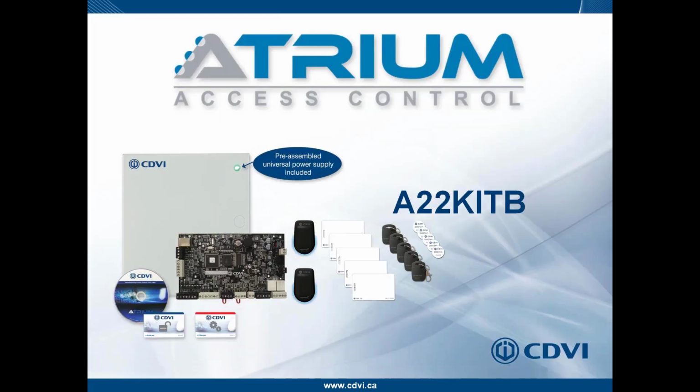And I just want to, what we're looking at here, here's an actual picture of the controller. This is the A22. The A22K is exactly the same as far as footprint, and in this particular case, the hardware we're talking about. And the 2 relays that we're talking about are the white relays on board. They're dry contact, Form C relays, whatever you want to call them, normally open, normally closed. So relay 1 and relay 2.